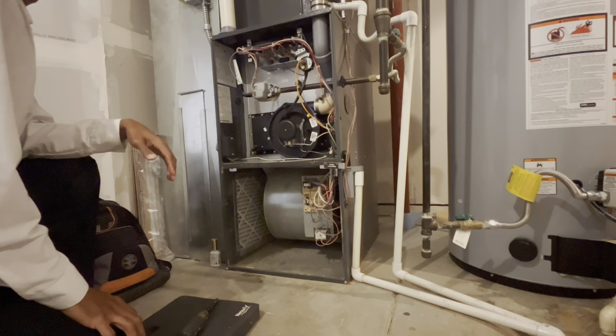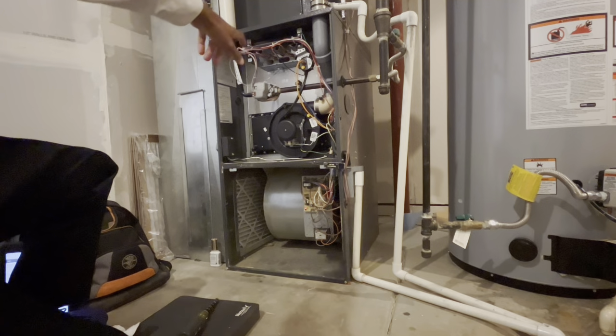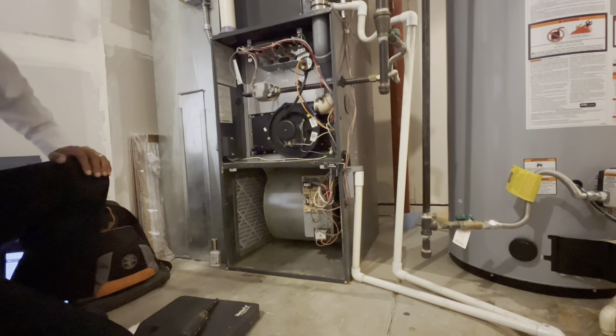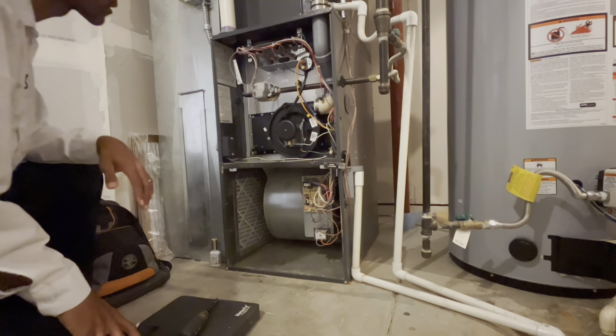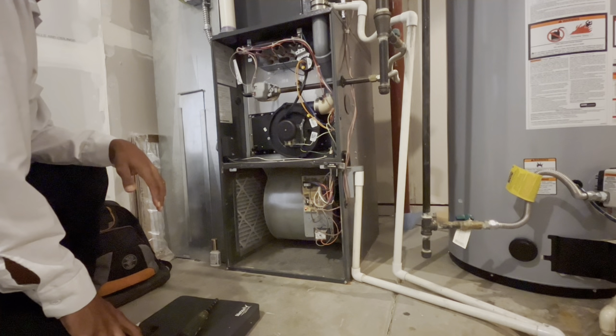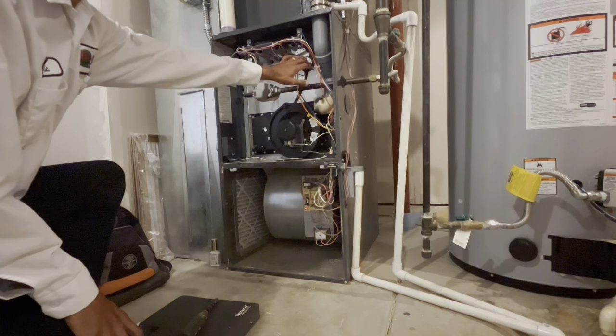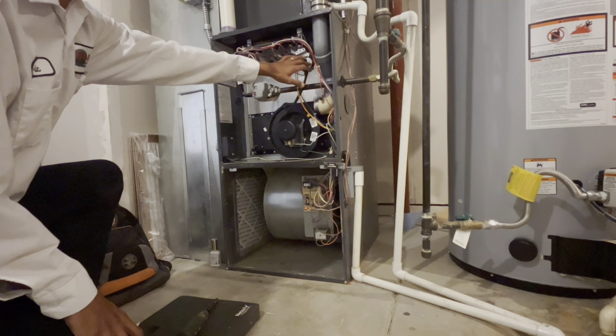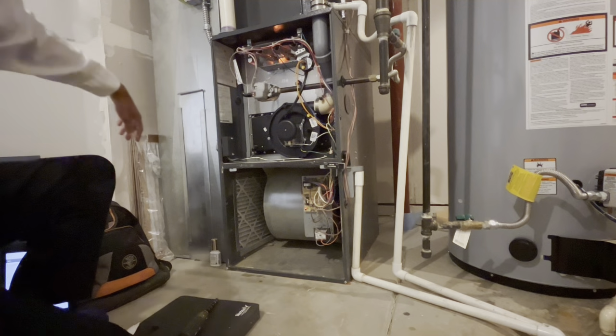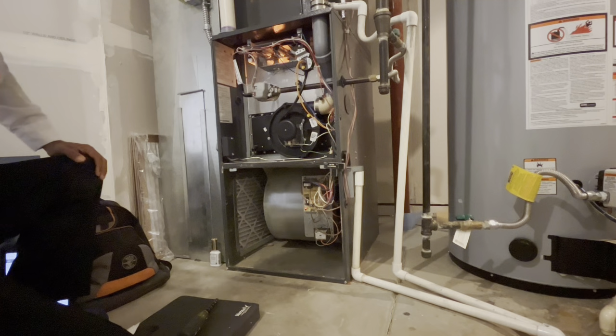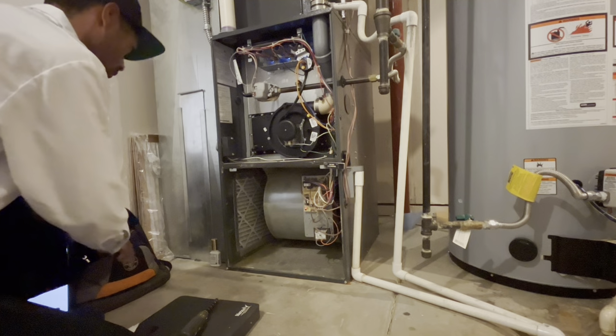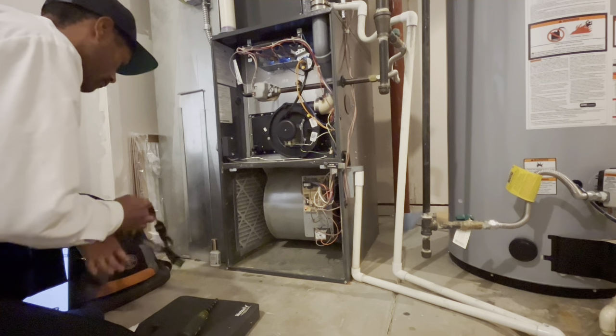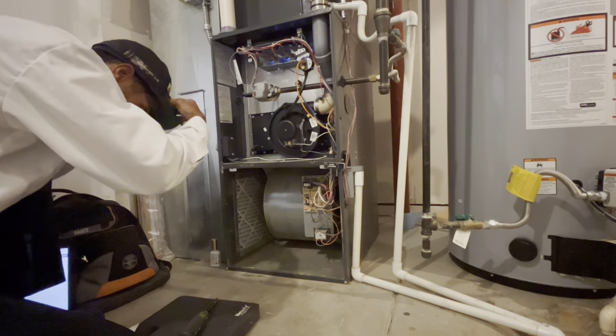I like to test the furnace out first to make sure that it does heat before I start taking everything apart. There's nothing worse than taking the whole system apart, putting it back together, then finding out that it does not actually work. So it's like the first little initial test that I do. You can see right here the igniter is glowing. So that means that the inducer motor already kicked on, the pressure switch is closed, the igniter glows, and then the flames turn on. Okay. After the flames turn on, the flame sensor senses the flame, then it kicks the blower on.